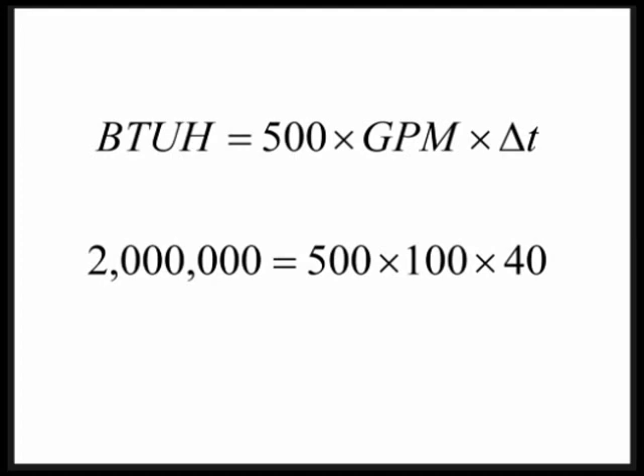Why 40 degree delta T? Remember, lower return water temperatures mean more efficiency. So instead of designing for 20, we're starting to see designers stretch to 30 and 40 degree delta T. It means smaller pumps, saves you some money. It also means lower return water temperatures, also saving more money.